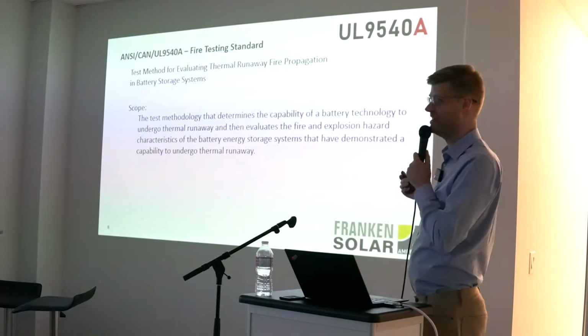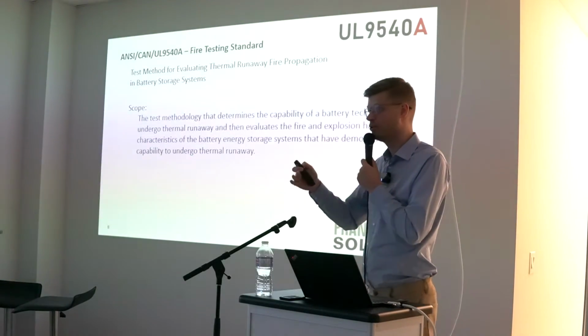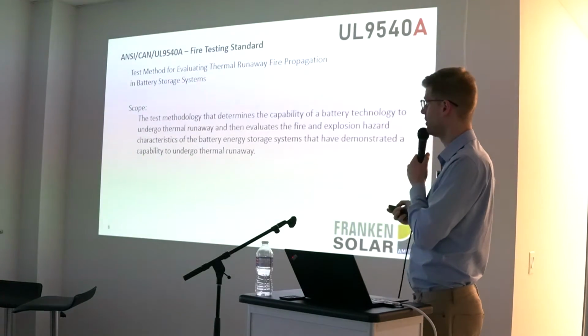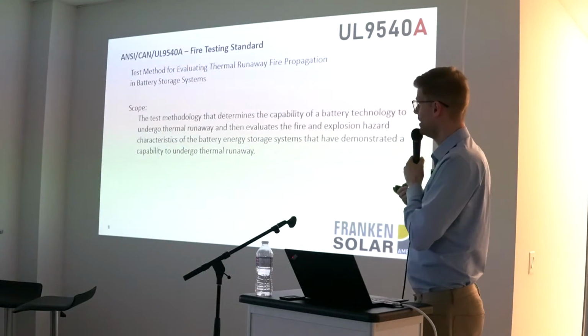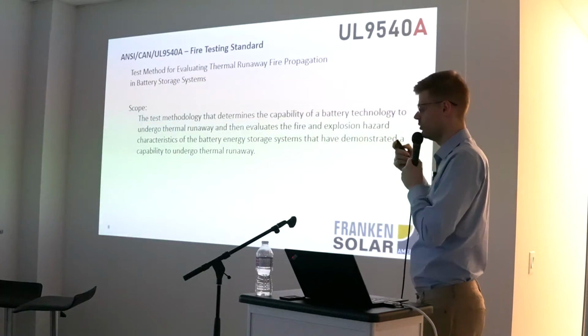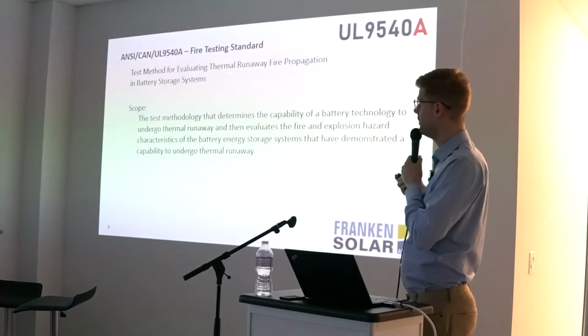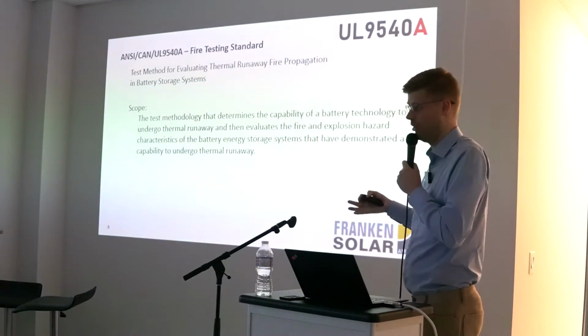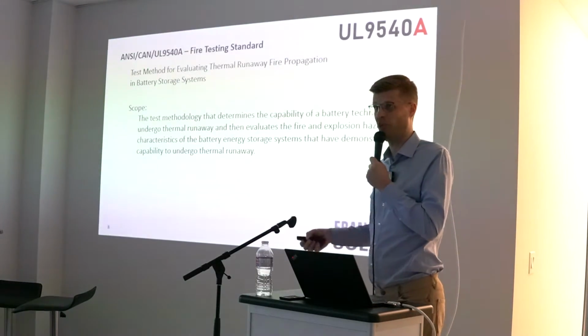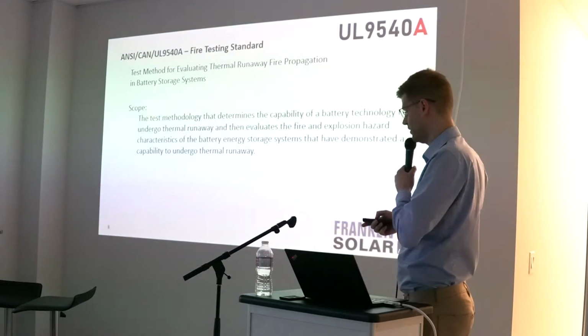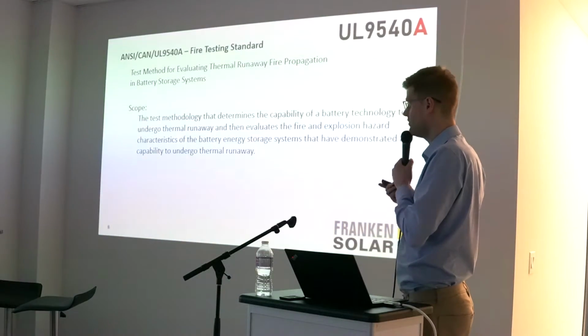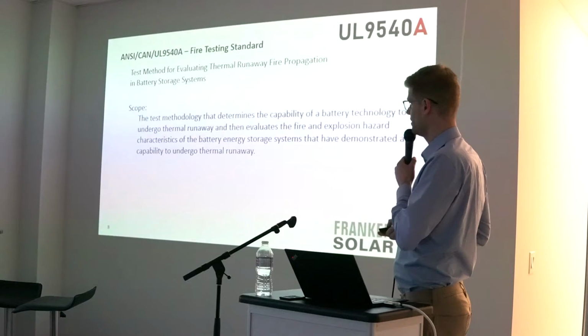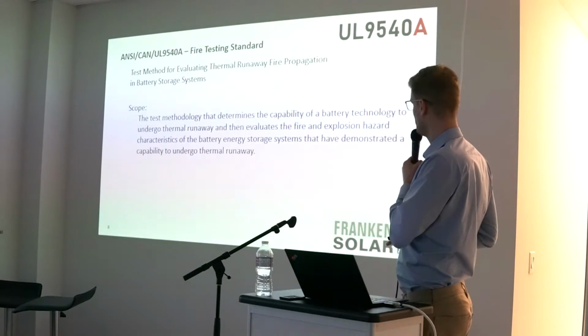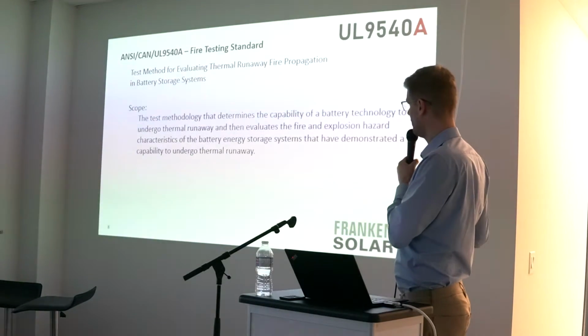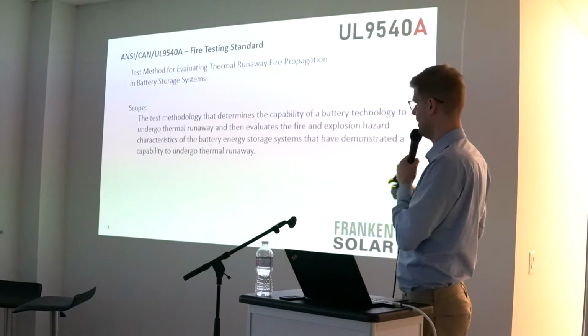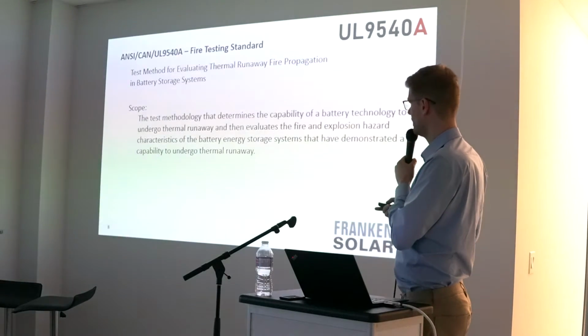We now add an A to the UL 9540, and now we come from the system certification to the underlying fire testing standard that is part of UL 9540. The fire testing standard is mainly a testing procedure to check what will happen in a thermal runaway, or if there even is a thermal runaway in the first place, and what the aftermath of that thermal runaway is in regards to safety and further fire-related or safety hazard-related things. So the scope, that's the definition, is the test methodology that determines the capability of a battery technology to undergo thermal runaway, and then evaluates the fire and explosion hazard characteristics of a battery energy system that has demonstrated a capability to undergo thermal runaway.